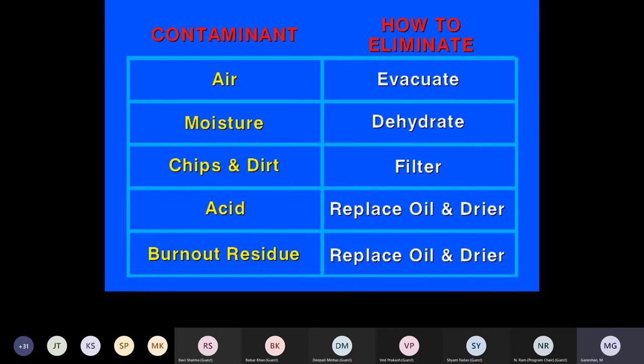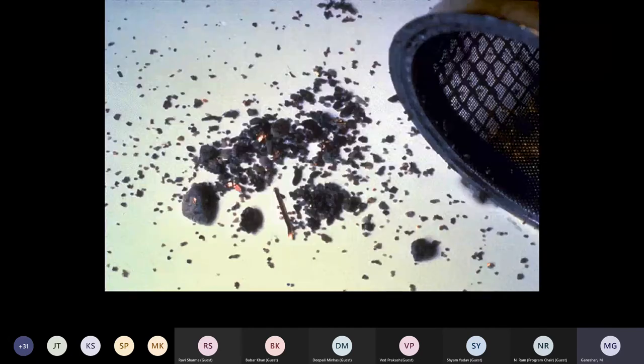Why does repeat failure happen? Because once a compressor has failed, there is so much internal debris and burnout residue that remains. If we don't properly clean it, flush it, and remove all those things, within no time it chokes the dryer, or it can even damage the compressors. So we should take care during the recommissioning. This is what we have practically seen.